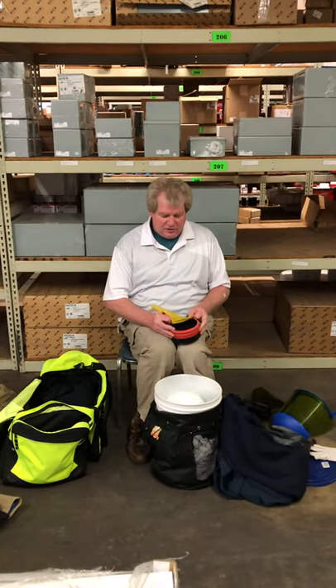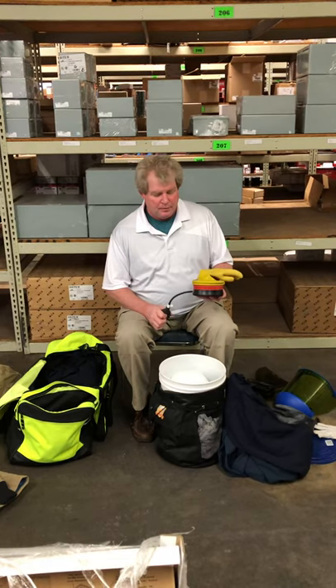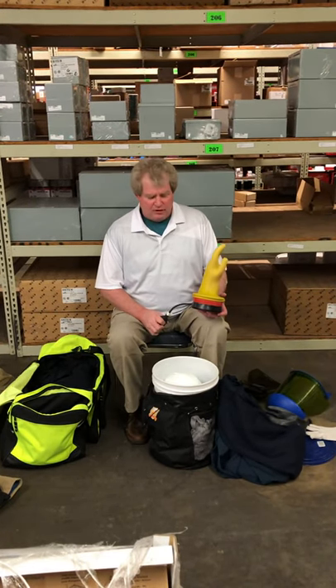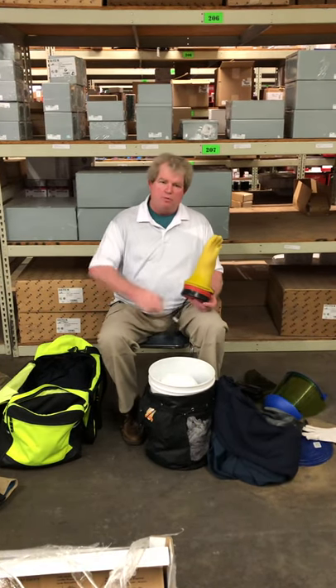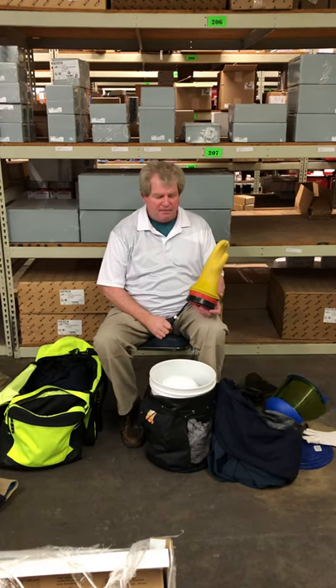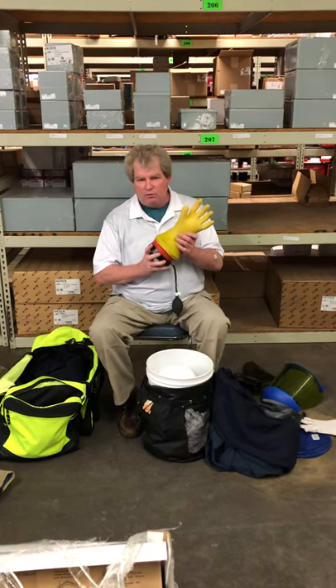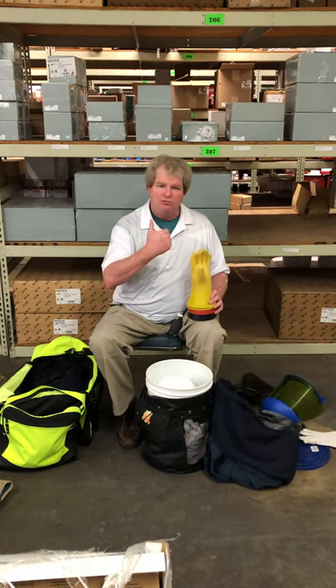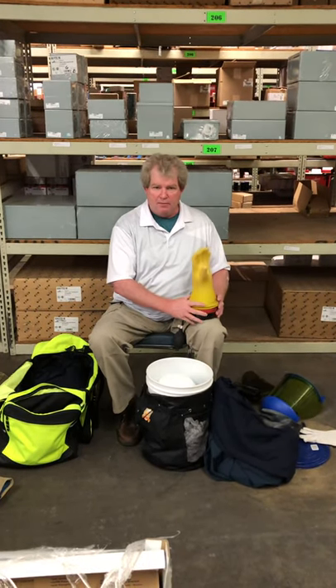The easiest way to check for functionality is to do a glove test using a glove pump. I'm a realist — blowing and rolling, inverting and stretching is what guys do out in the field. We do what's called a sign-up log: we put their names and all the weeks of the year, and each week they have to come in and sign off that they put each glove — right and left — on this pump. The reason we do that is so at least once a week they're checking them properly, which reduces our liability. We'll blow and roll in the field, and once a week come in and use the pump to verify.